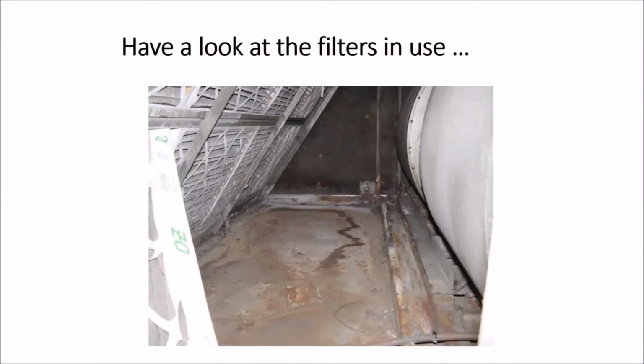And here's what I mean by a picture is worth 1,000 words. Here you see on the left-hand side, there's a filter that's been bent, so the air is actually passing around it. You also see other problems. You see evidence of moisture and dirt, and perhaps even mold growing in some of these things. And taking a picture will make a better argument than saying this in words.